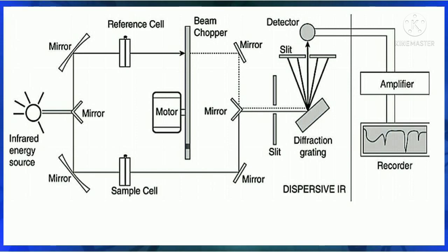Now then there is the monochromator. Well, we generally use a prism as a monochromator, which is generally made up of alkali metal halides, say NaCl, KBr, LiF. Apart from prisms, we can also use gratings. Well, what are these? These are nothing but small tiny prism-like structures which act as a monochromator. Well, gratings are generally an advanced version of monochromator. Why am I saying it is an advanced version? As it is generally made up of materials like aluminium which are not attacked by moisture. So it is more advantageous, and it also covers a considerable wavelength range, so it can absorb most of the wavelengths, so it is more preferred.